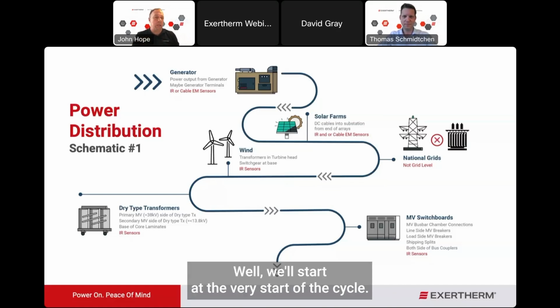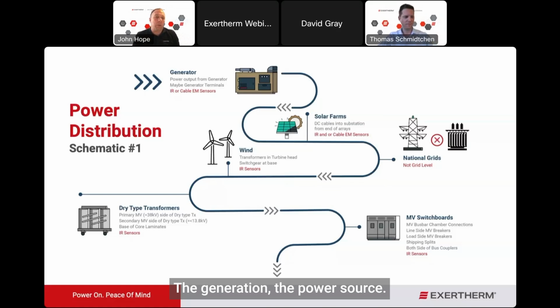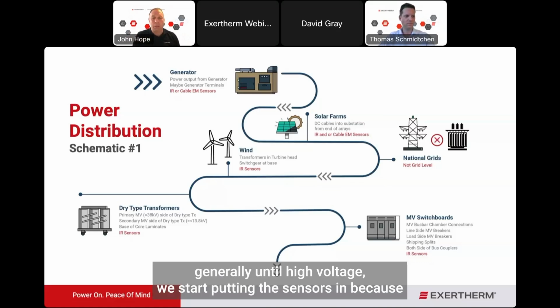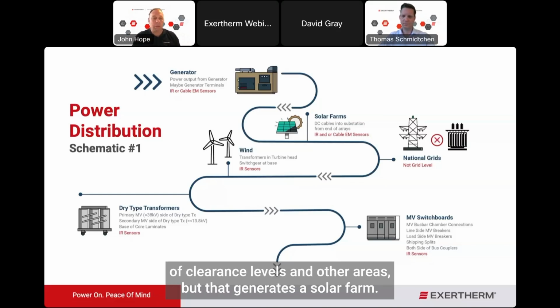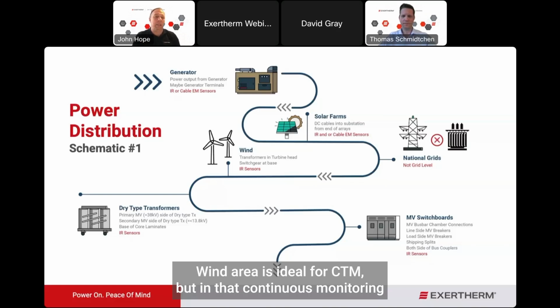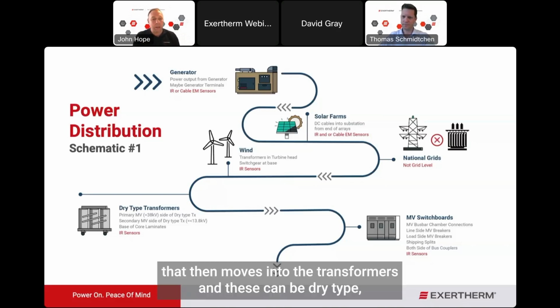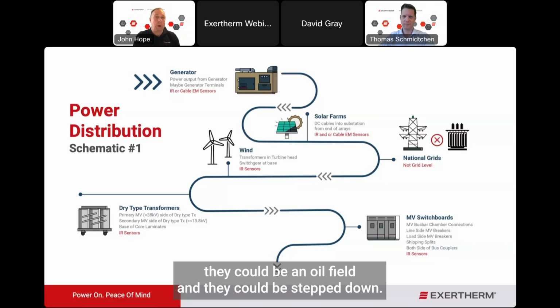Well, we'll start at the very start of the cycle, the generation, the power source. We can have CTM within generator systems, within solar farms or wind farms. There is suitable voltage for this. If we look actually to the grid, it generally is too high a voltage to start putting sensors in because of clearance levels and other areas. But that generator, solar farm, wind area is ideal for CTM, adding that continuous monitoring. That then moves into the transformers, and these can be dry type, they could be oil filled, and they could be step down, step up. Again, that's an ideal point for CTM.